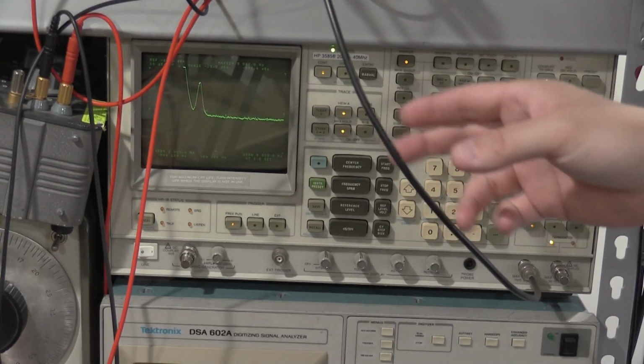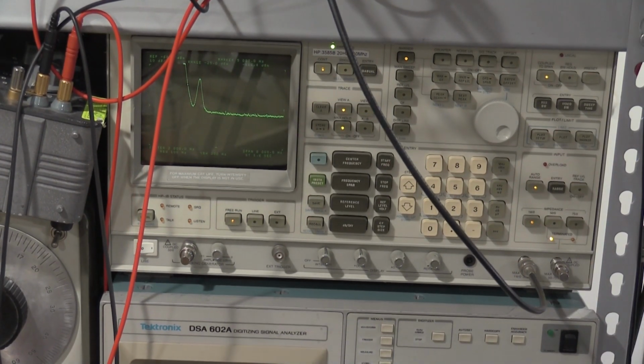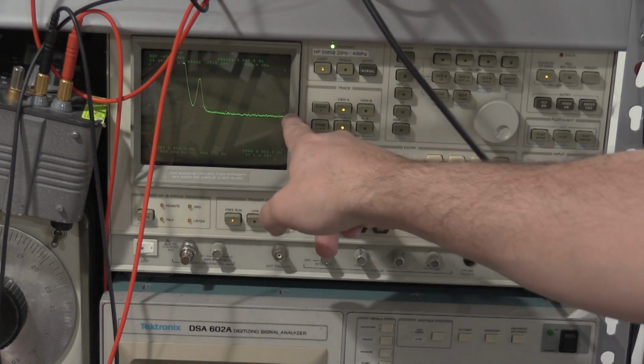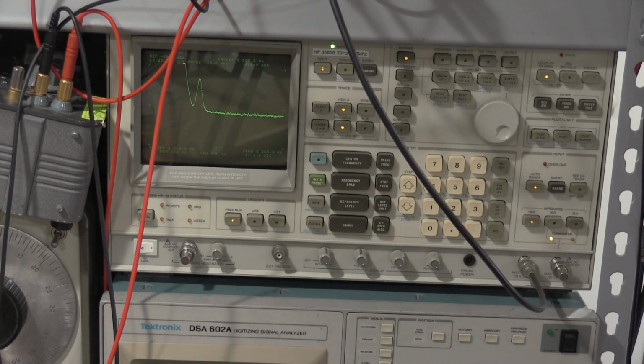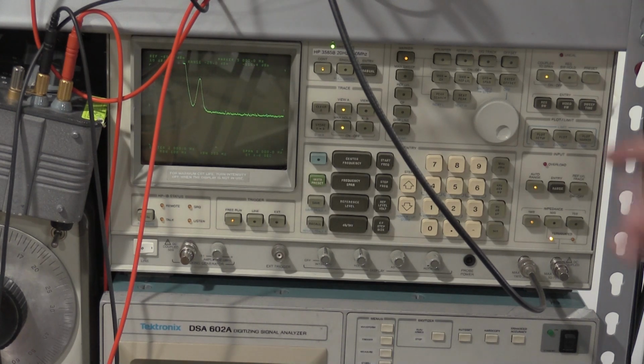Pardon the cables everywhere. This is the input coming in from the notch filter. I notched out the fundamental as much as I can. We do still see some fundamental. And the document wants us to look at up to the 5th harmonic. We're on 1 kilohertz, so we're going up to 8 kilohertz over here. Our 1 kilohertz signal is here. And then here's what we have for harmonics. Reference level is a negative 60 dBm, and as is always important, we're not overloading the input.